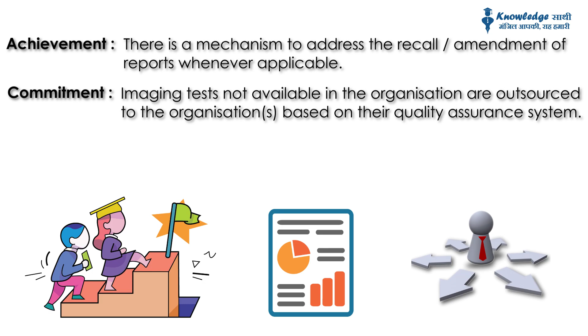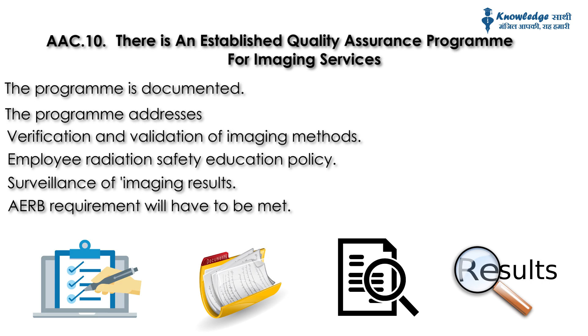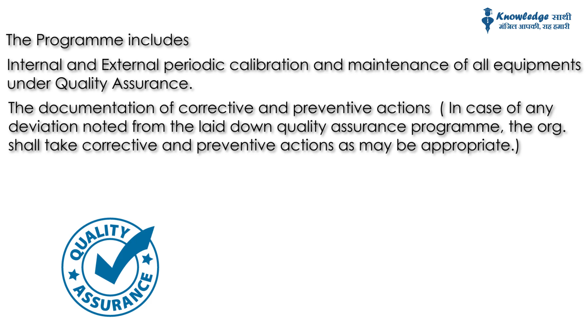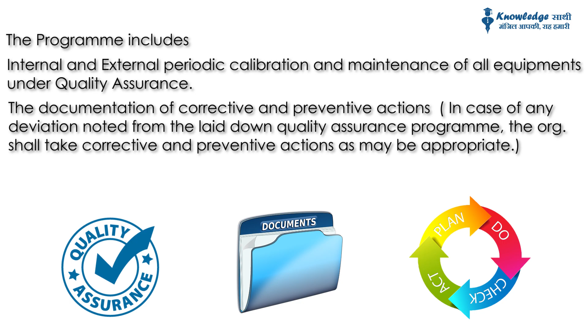Number 10. There is an established quality assurance program for imaging services. The program is documented. The program addresses verification and validation of imaging methods, employee radiation safety education policy, surveillance of imaging results, and AERB requirements should be met. The program includes internal and external periodic calibration and maintenance of all equipments under quality assurance, the documentation of corrective and preventive actions. In case of any deviation noted from the laid down quality assurance program, the organization shall take corrective and preventive actions as may be appropriate.